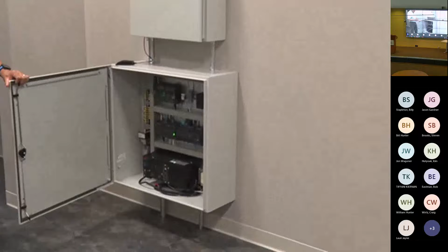Now, all of the systems that you saw there are being brought together on the network, but a lot of processing and building control has to be done. And where it's being done is cabinets like these. There would be a number of these mounted on different floors of the hospital, and they would contain building controls that are programmable, lighting controls, window shade controls, things that would allow us to do all the types of functions that we need to do within the hospital, and some of the things we'll talk about in the smart patient room in just a minute. All backed up by UPS to make sure that there isn't an outage within this cabinet.